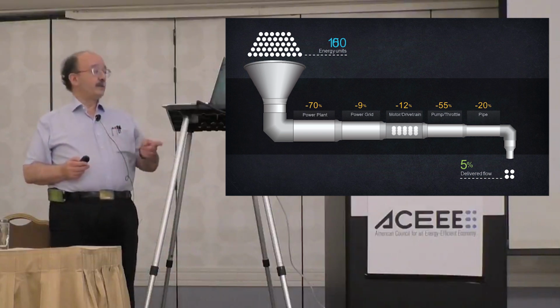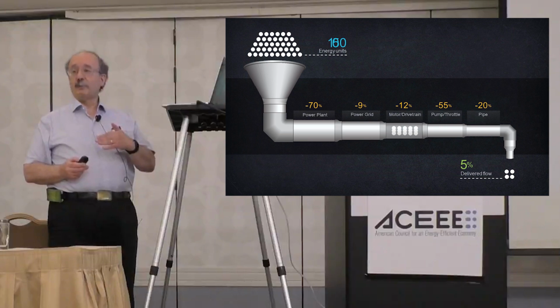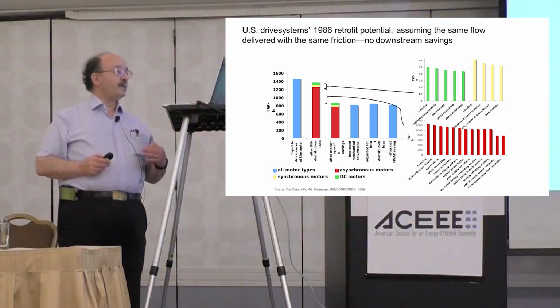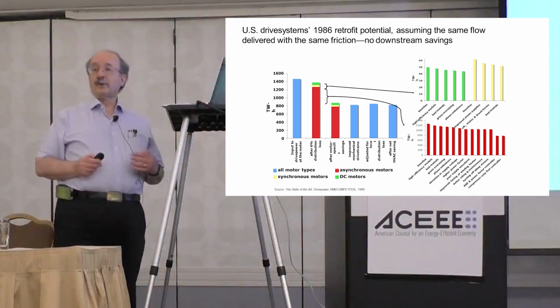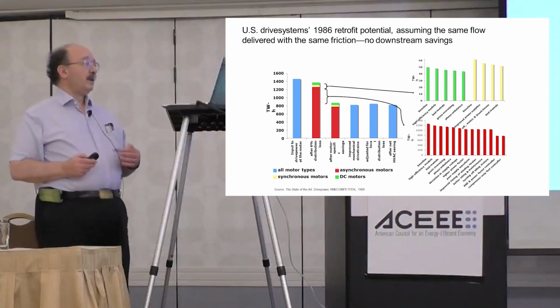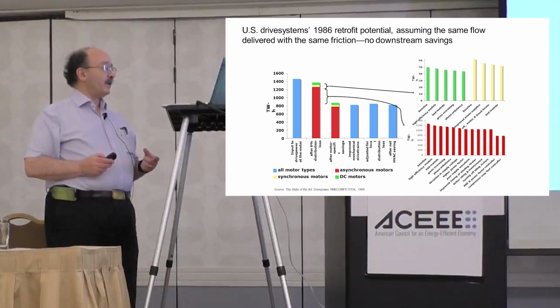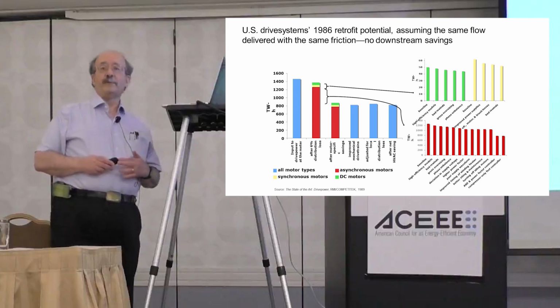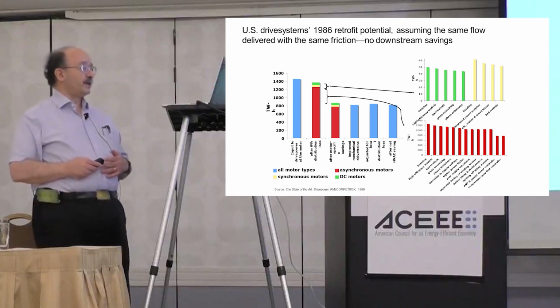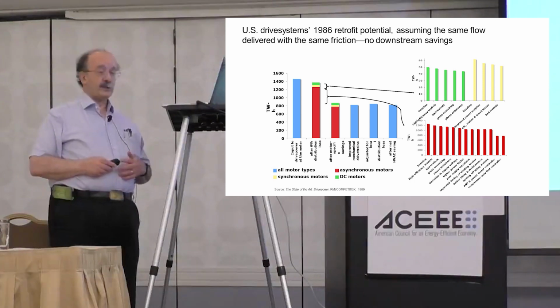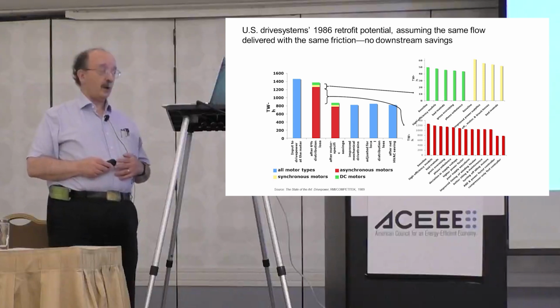Also, as you go back upstream, the components get smaller and cheaper, so the total capital cost goes down. So while you're making the pumps and fans and motors about 5 or 10 times smaller, you can also do 34 other things to the motor systems that collectively save roughly 3 to 5 times more energy than just the 2 usual improvements - high efficiency motors and adjustable speed drives.